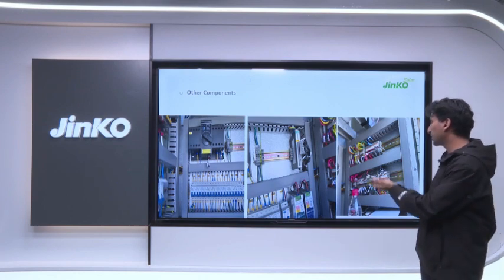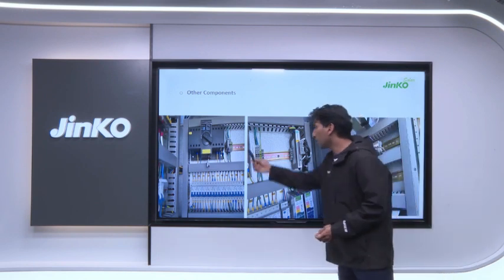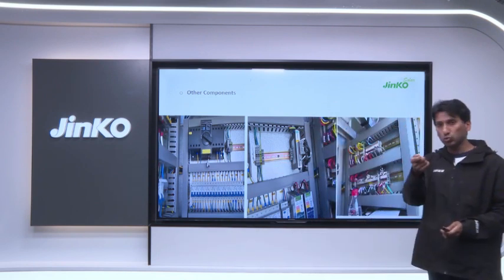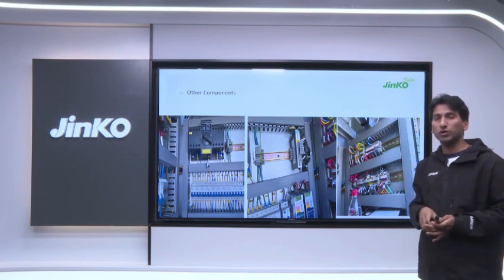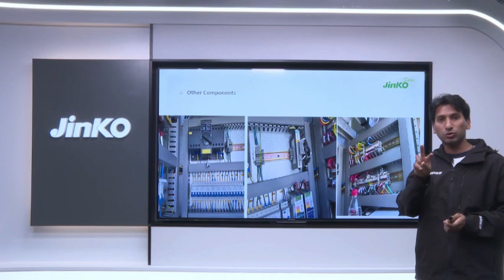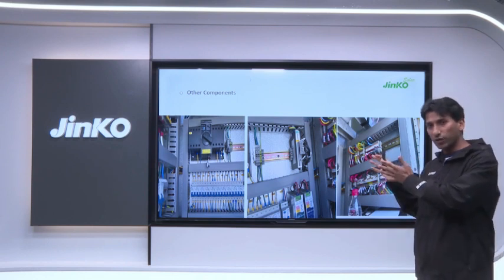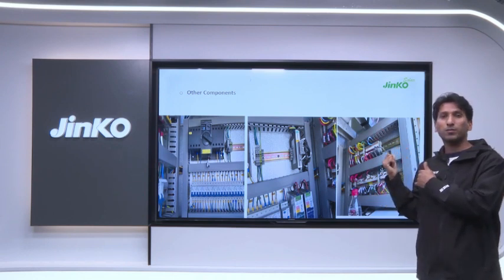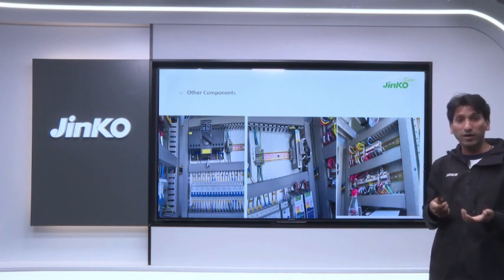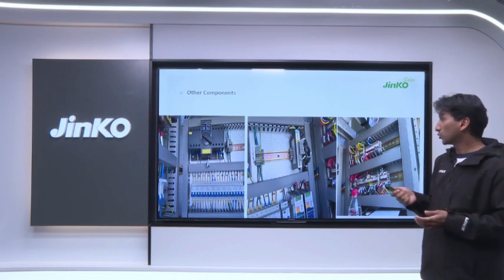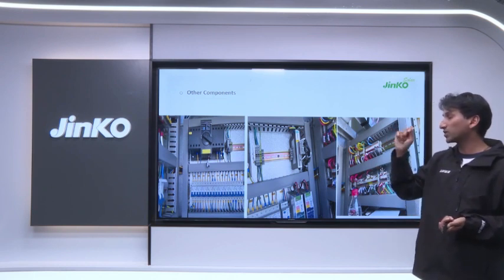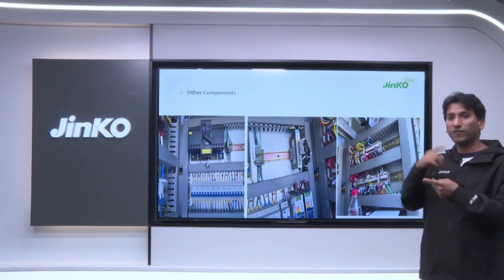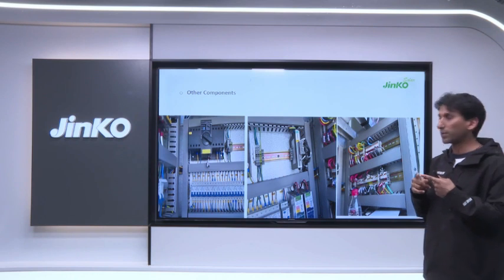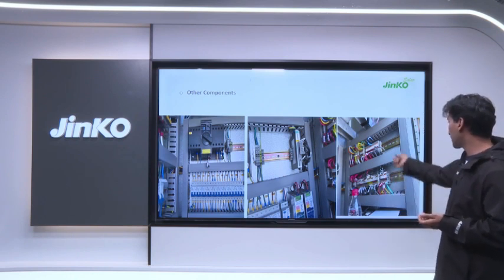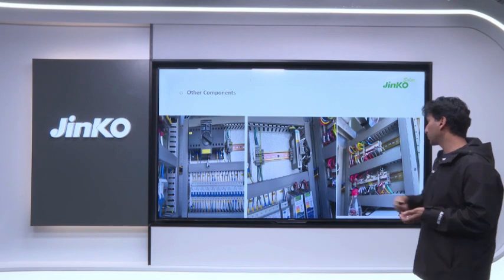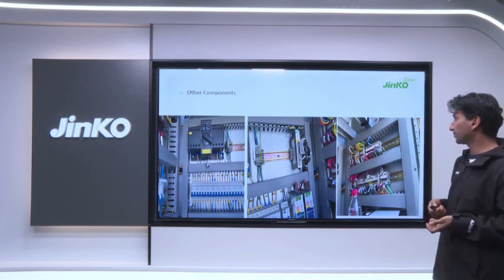These are other components in the integrated cabinet. If you see this switch, this is for the fire extinguisher system. This is a two-pole switch. Why do we use a two-pole switch? Because the fire system needs two power supplies. One it takes from the UPS, and the other we connect from the external power supply, in case the customer or the site design requires it, so that if something happens with the UPS and there is no power, the external power can be used, and the fire extinguisher system keeps working all the time, because it's very important. And these are some other components. This is for the RS485 switch, and there are some other MCBs.